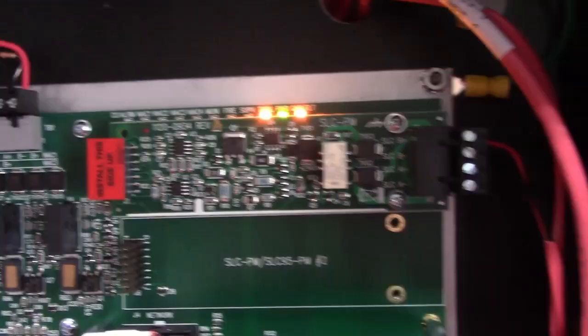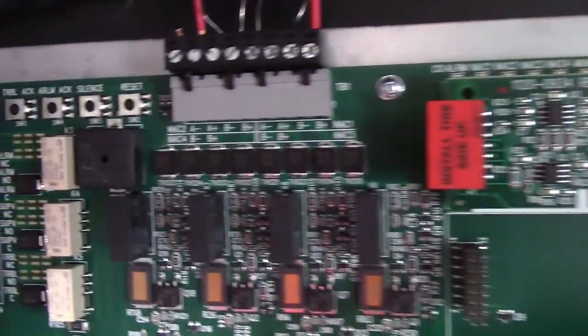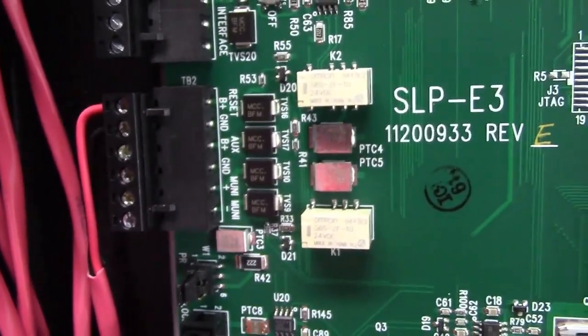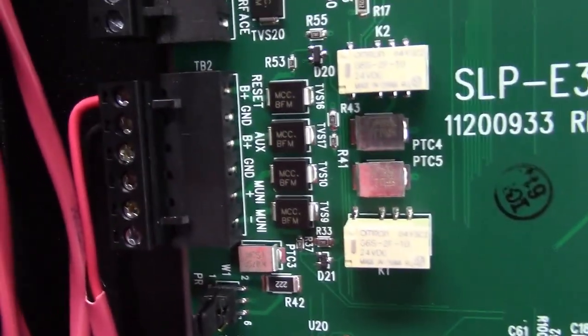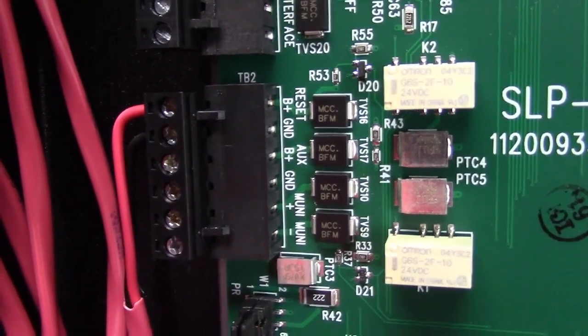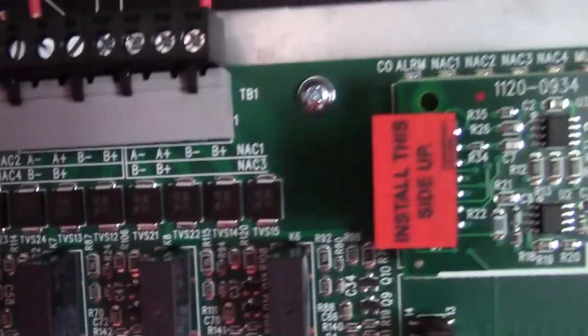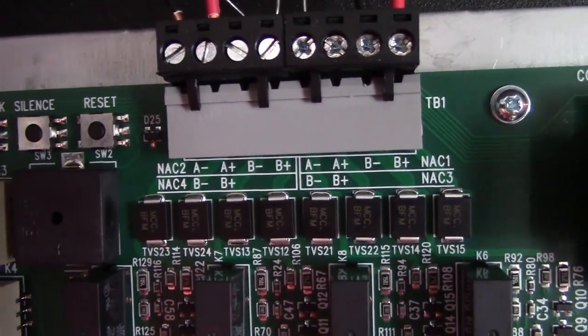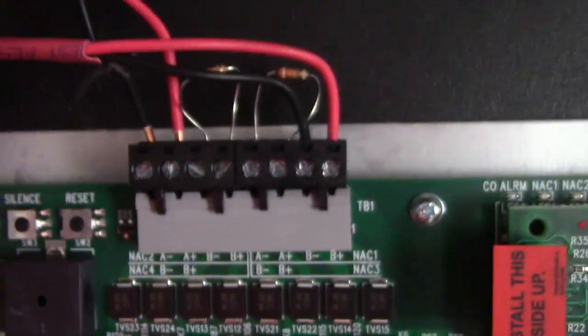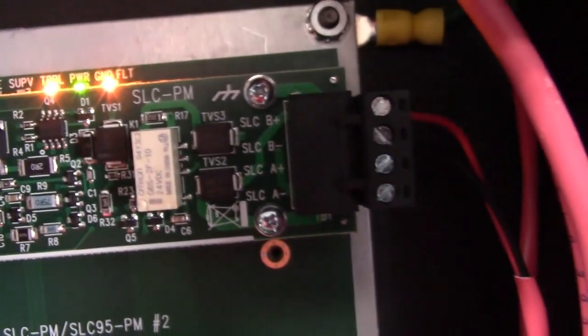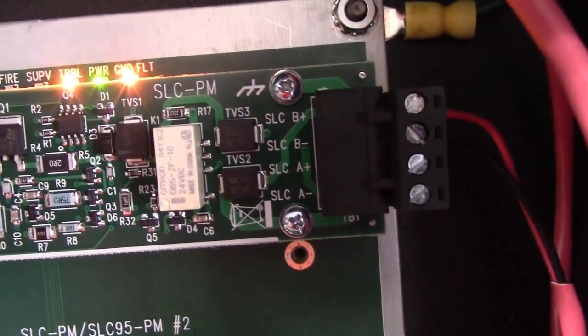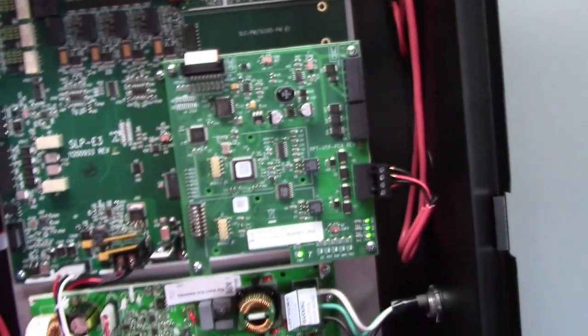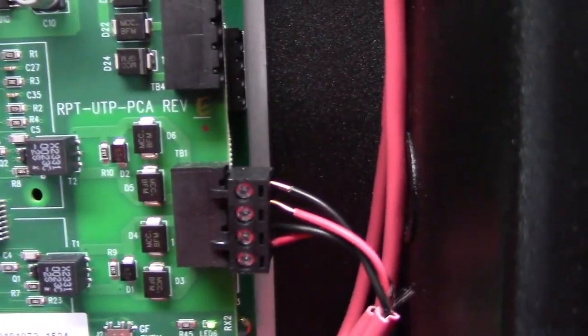So in a moment, we'll try and isolate which circuit from the panel has the issue. So starting over here, that's auxiliary power output to power something outside the fire panel. These are notification circuits. NAC stands for notification appliance circuit. It could be on one of those circuits, and it could be on the signaling line circuit that goes through all the addressable detectors. Finally, this panel is equipped with a network card, and it could perhaps be on the network connections.